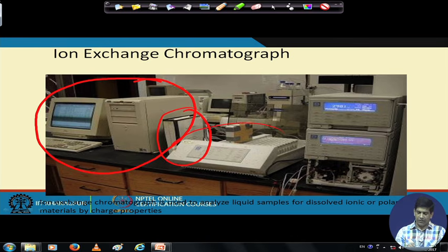This part is our auto sampler. You can prepare several samples, and here you can see several holes where you can put all your different samples, and those can be analyzed in one go. You set up your sample, you set up your instrument, and it will be analyzing for 5 hours, 6 hours. You can come back and check on it from time to time. With the newer version, you can even watch it using your smartphone. There is an app where you can look at how the machine is working, and you can even shut down the machine using that app, but you cannot restart it, so you have to go back to the lab to do that. But there are a lot of new things happening.